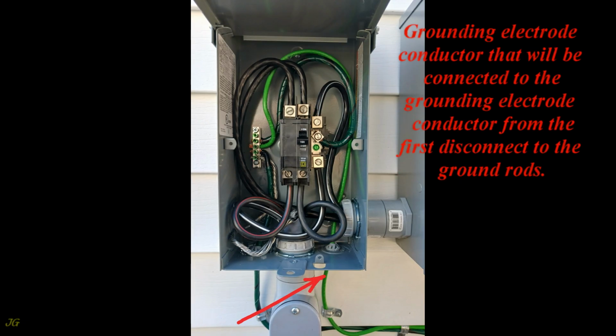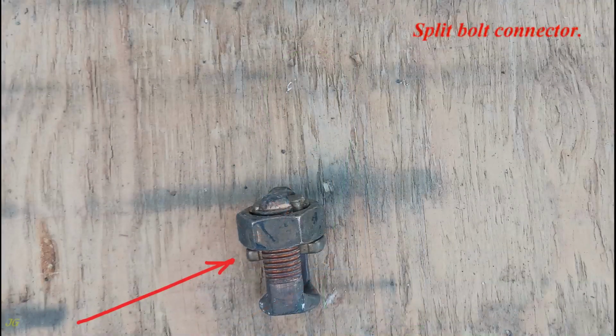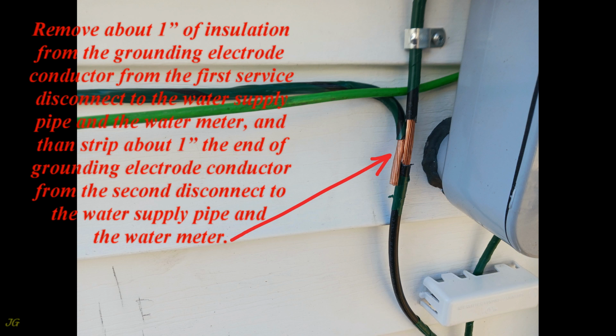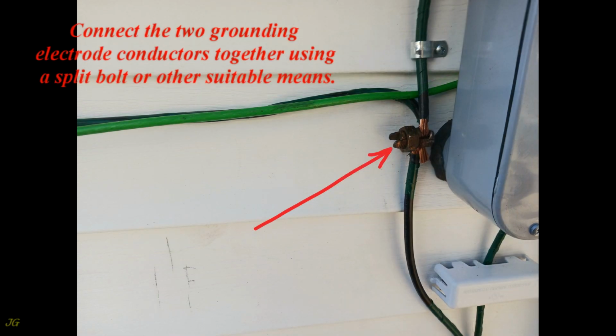Grounding electrode conductor that will be connected to the grounding electrode conductor from the first disconnect to the ground rods. Split bolt connector. Remove about 1 inch of insulation from the grounding electrode conductor from the first service disconnect to the water supply pipe and the water meter, and then strip about 1 inch of the end of the grounding electrode conductor from the second disconnect to the water supply pipe and the water meter. Connect the two grounding electrode conductors together using a split bolt or other suitable means.